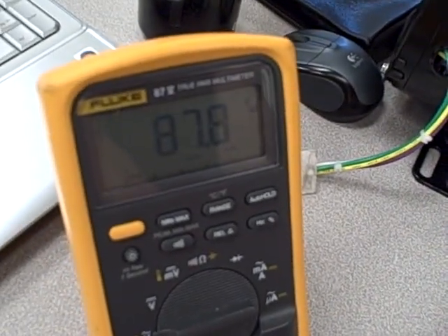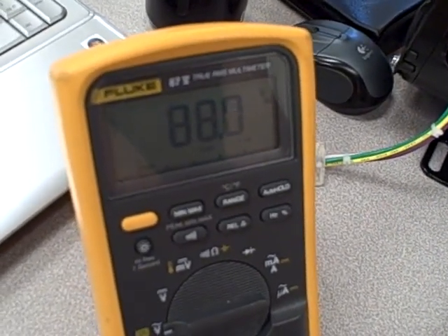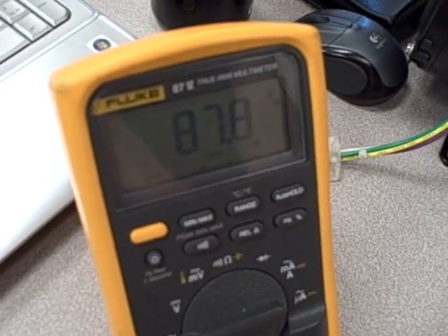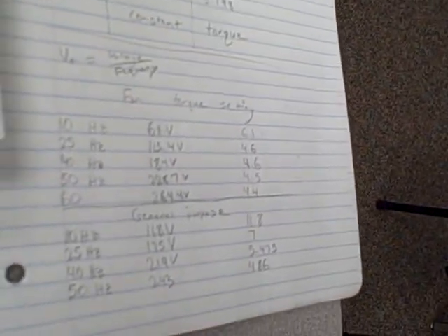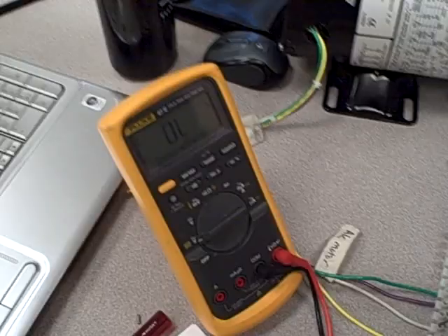So what's happening here is it decreases the voltage in proportion to frequency. They call it the V to F ratio, or the volts to hertz ratio. And what do we calculate there for V to F? Is it like 4.6 volts per hertz? 4.6. Yeah, and it's almost a constant 4.6 volts per hertz, looking at that table right there. It's calculated with the different voltage readings and frequencies that we got in this particular setting.